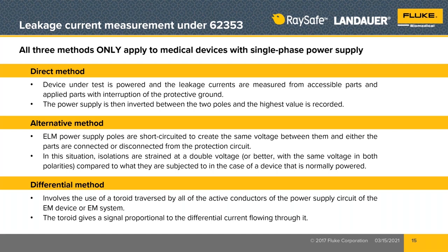what they are subjected to in case the device is normally powered. In the differential method, we would use a toroid transformer traversed by all of the active conductors of the power supply circuit of the electromedical device or system. The toroid gives a signal proportional to the differential current flowing through it. Now, does that mean you have to go out and buy a toroid? No, no, no, no. Not when you use Fluke Biomedical test instruments. All of our electrical safety analyzers, when we're using the 62353 differential method, already take into account that toroid. It's built in. So you don't have to worry about that. So how will we make the choice then among these three testing methods that are available?